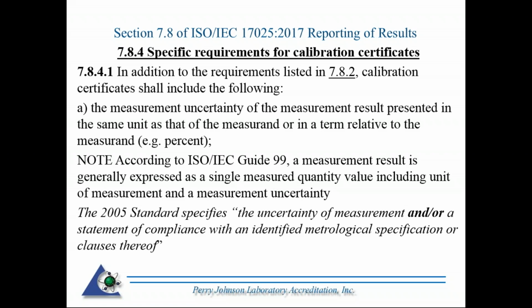So I have a reference to ISO Guide 99 there. A key difference: the 2005 standard stated the uncertainty of the measurement and/or a statement of compliance. That comes out of the 2005 standard. Now you see 7.8.4.1. We don't see that "and/or" anymore. It specifically states the uncertainty. So that is a specific requirement directly coming from the standard now for calibration laboratories.